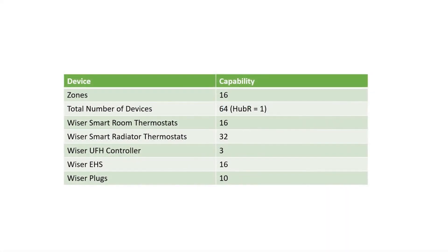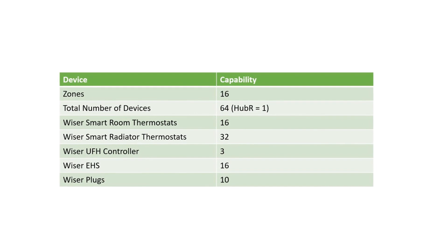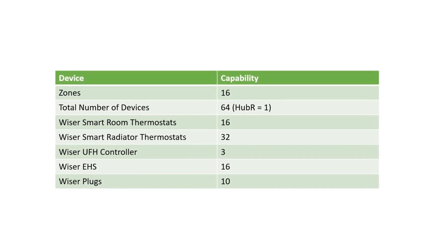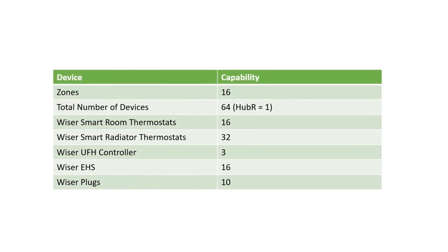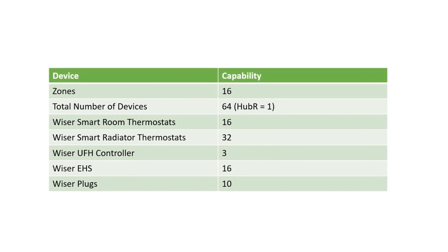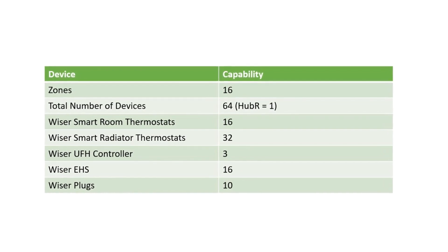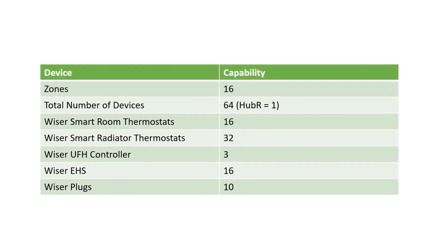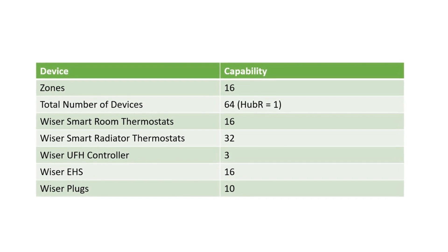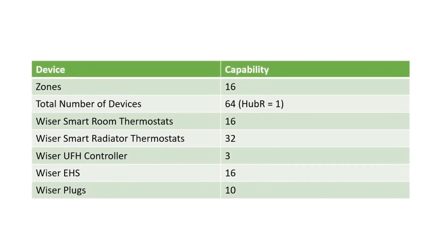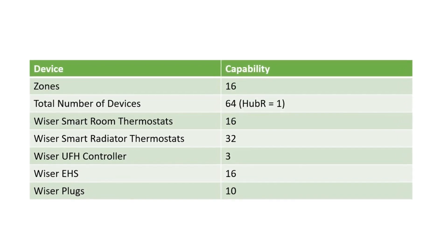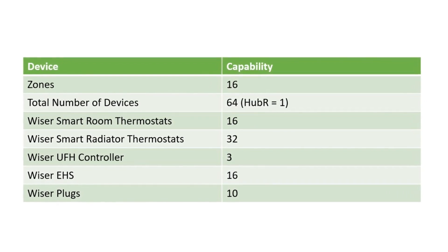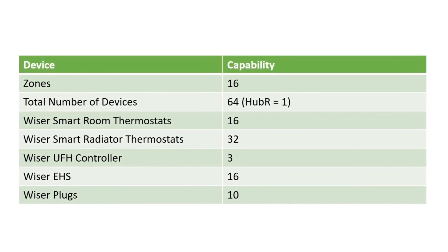It is important that you stay within the device capability of Wiser: a maximum of 16 zones, 32 Wiser radiator thermostats, and 16 Wiser room thermostats. These room thermostats can be assigned to a standard central heating zone, the Wiser underfloor heating controller for multi-loop wet underfloor heating, or the Wiser electrical heat switch.